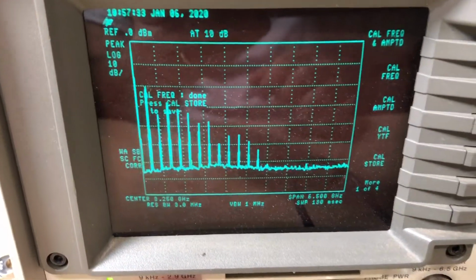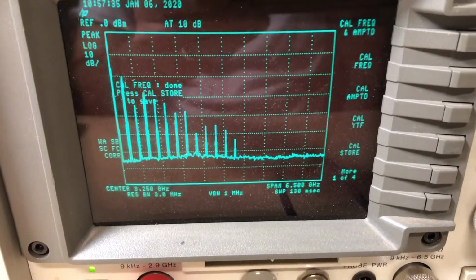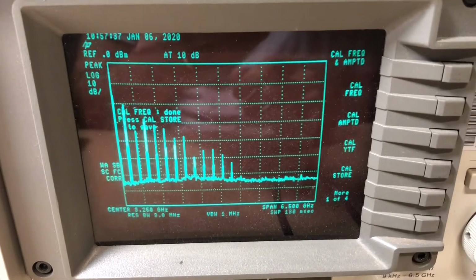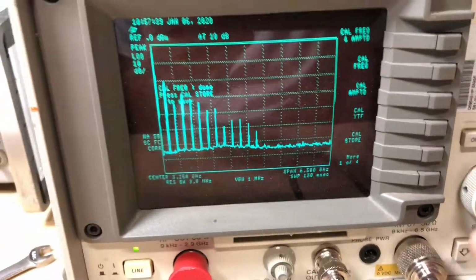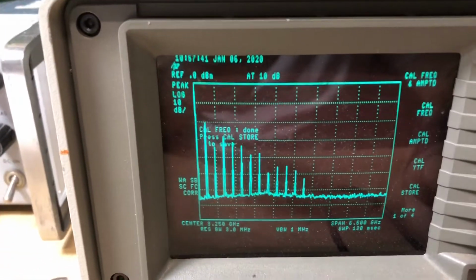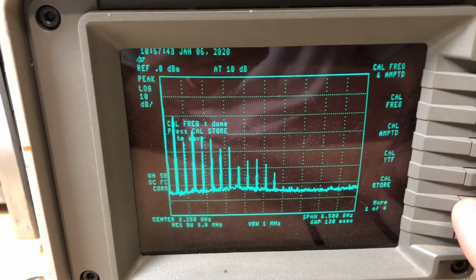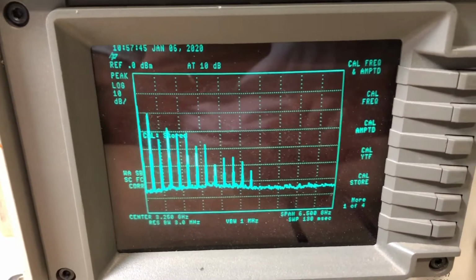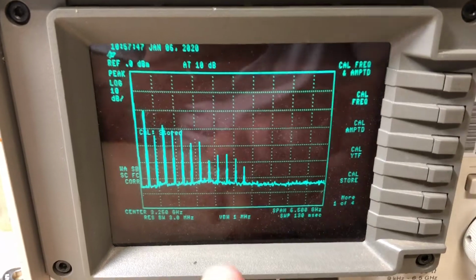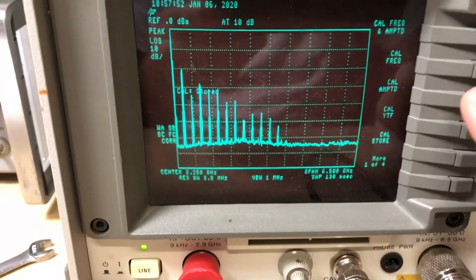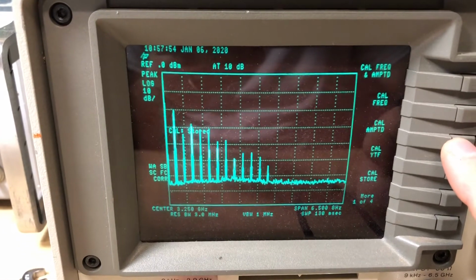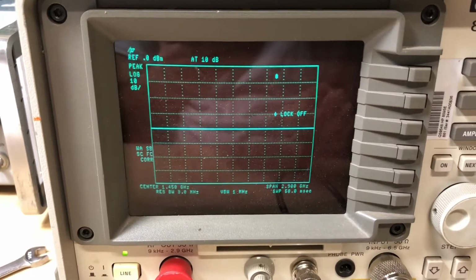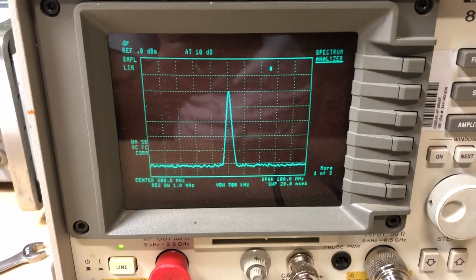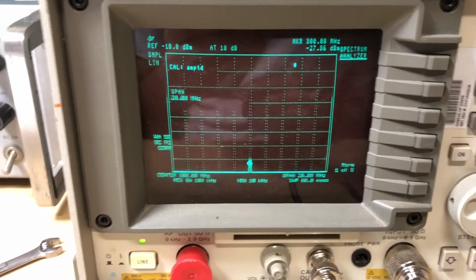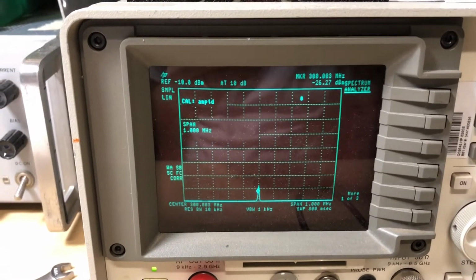All right, and our cal frequency is done. It did not bring up any errors. We will go ahead and hit the cal store, because you have to store the values every time you run the routine. And there we go, we got the cal stored message. All right, so now we're going to do cal amplitude. And I think this routine runs a little bit longer than the cal frequency. We'll look at the results when it's done.